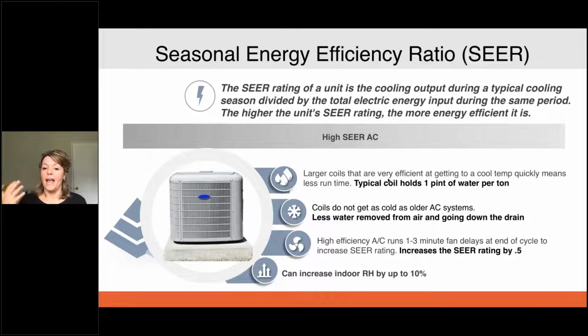And how they kind of sneak in a higher SEER rating is when the compressor shuts off, the fan runs for 1 to 3 minutes afterwards. And basically they're getting points for evaporative cooling. So if you live in Arizona, that evaporative cooling could be a big benefit. But if you're living in a more humid climate, all that moisture that's on those coils gets re-evaporated back into the air, which again, if you have a 5-ton system, that's 5 pints or pounds of water being blown back into your living space, and it can actually increase the relative humidity by up to 10%. So it's important to know how these higher SEER systems are working when it comes to moisture.